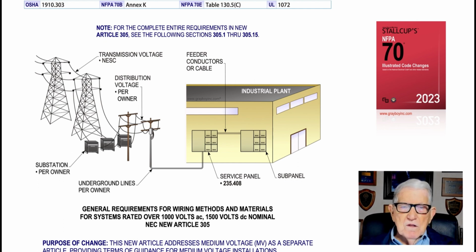But now, notice one thing, that there are 5 new articles that deal with systems over 1,000 volts and medium voltage type systems. Article 235 is branch circuits, feeders, and services. Article 245 now is overcurrent protection, which used to be in Article 240, the last part. Article 305, we're just reviewing it. It's wiring methods and materials. And then, of course, Article 315 is joints and terminations of these wiring methods. And then 495 is the existing article of 490. So the purpose of this change mainly is just to provide articles that deal with medium voltage and specific types of equipment and devices and components and so forth.